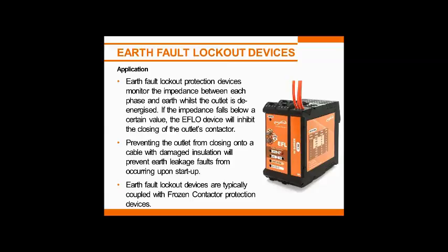And as I say, this is typically connected to a frozen contactor. We just have a look at some of the things here. This relay has an inbuilt barrier to connect to the high voltage, and it's capable of up to 3.3 kV. At the moment, we have a 1,000 volt system up and running. The 1,000 volt barrier will not only look at 1,000 volts, it looks at 500, and it looks at 240, and 110 as well. So there's a voltage switch here that you can switch to whatever voltage range you're looking at. There's also a back EMF time set at this switch. The frozen contactor indications are here, and we'll talk about those later. The earth fault lockout problem faults are displayed in this area here. Once again, there's a status light to tell you how the relay is going, and a little information on the side of the relay talking about the relay's operation.